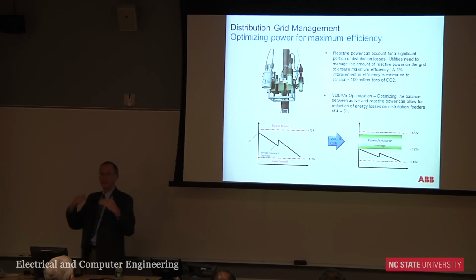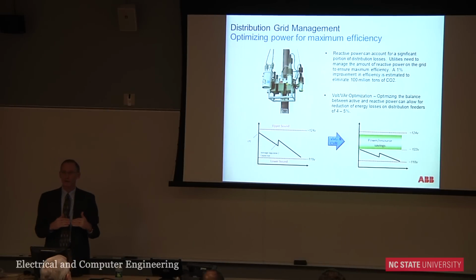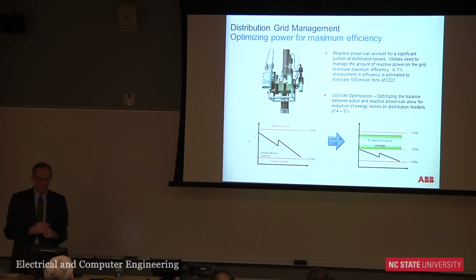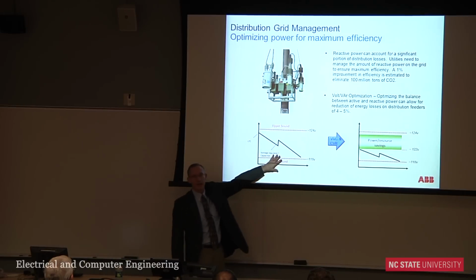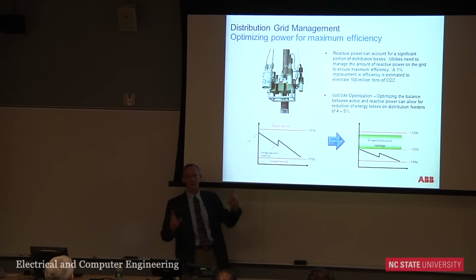That further reduces the load on the feeders, frees up additional capacity, or requires less T&D capacity and less generation capacity. That's called conservation voltage reduction. There are two processes: controlling VARs and volts, primarily related to capacitor banks, though load tap changers and line voltage regulators also come into play, and then actually lowering the overall voltage once you have a flatter voltage profile, which is the conservation voltage reduction.